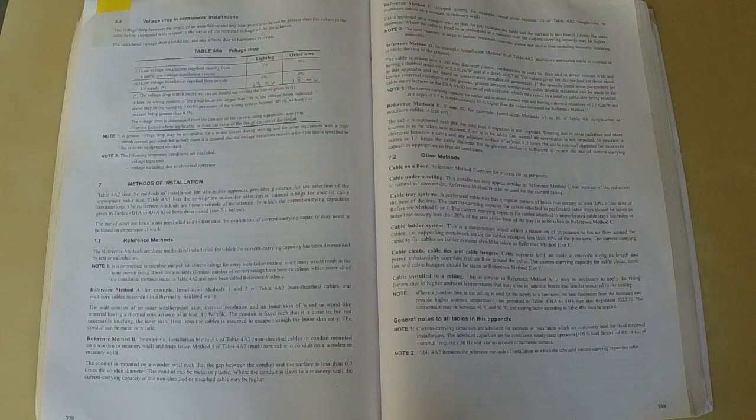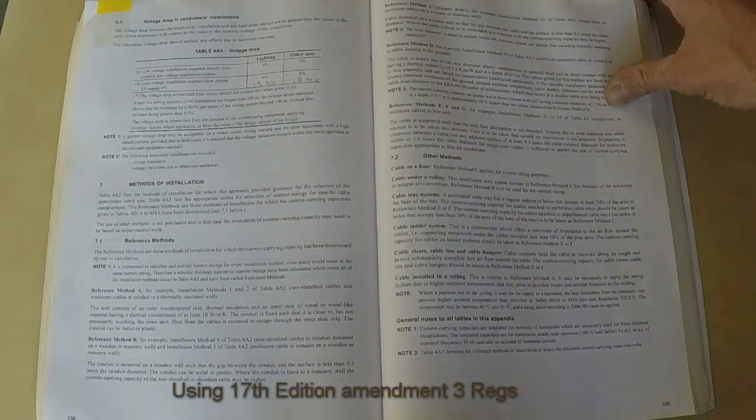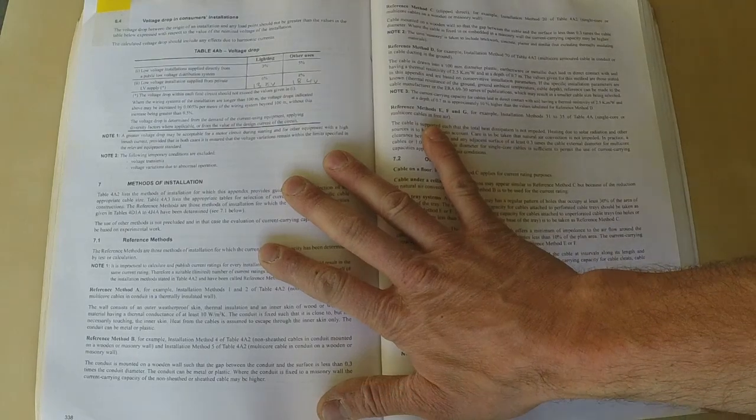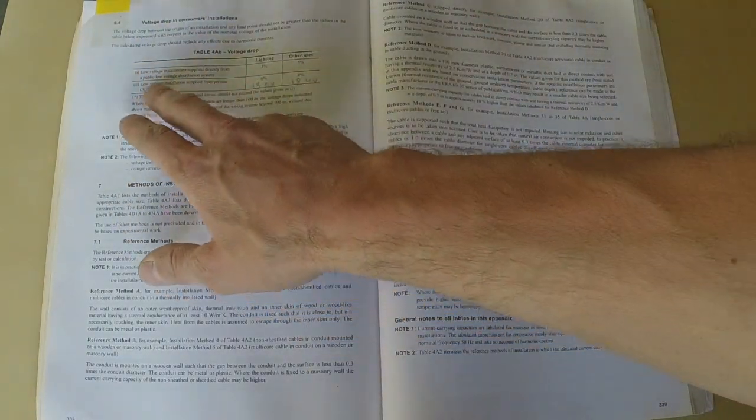Firstly you'll need a regs book and a calculator. Appendix 4 is about volt drop, and in this regs book page 338 shows the voltage drop allowed which in a private supply for lighting is 6%.